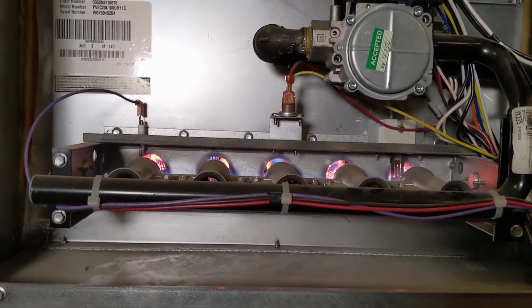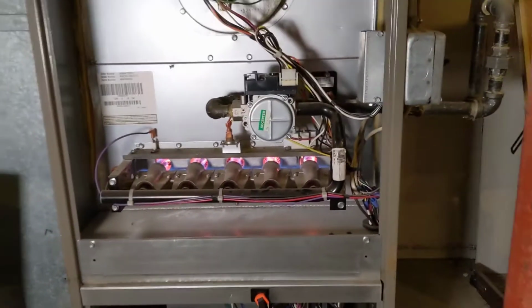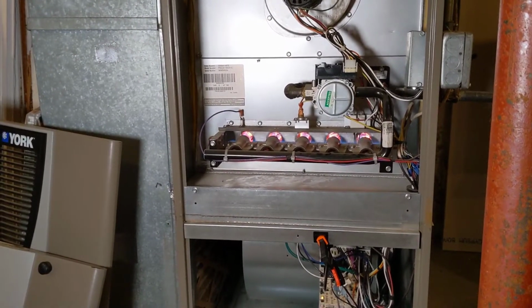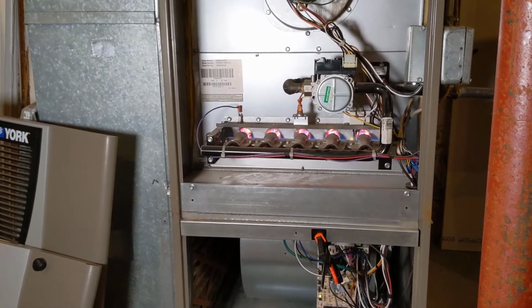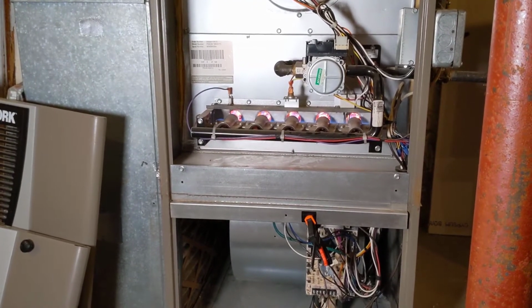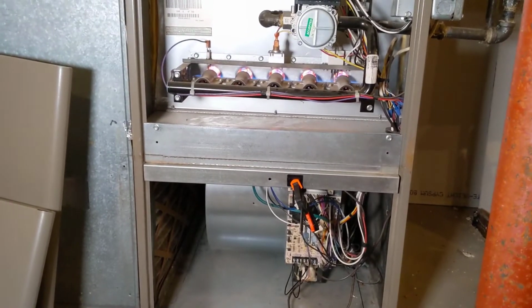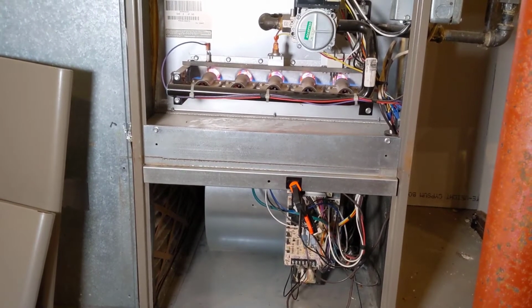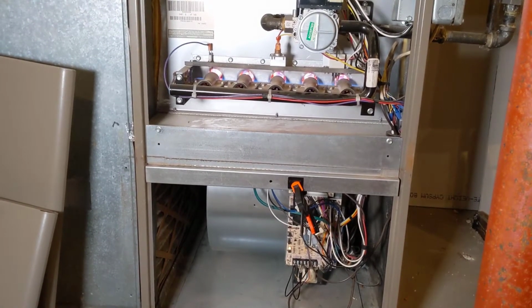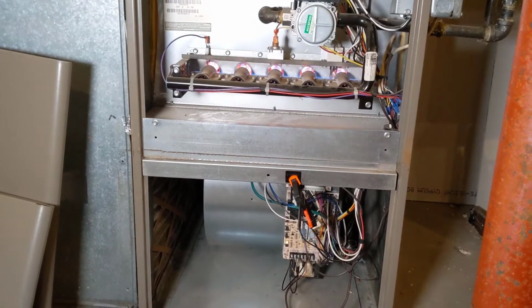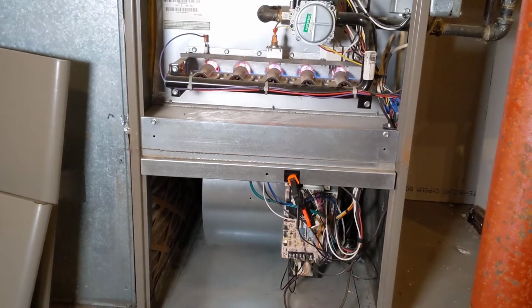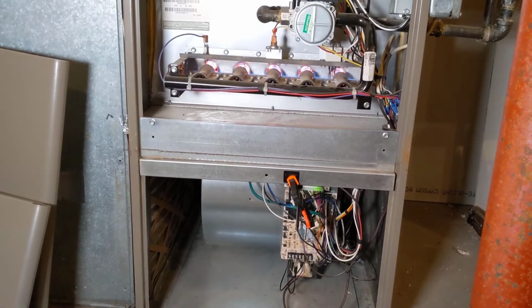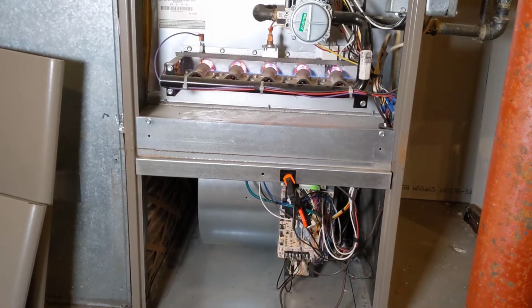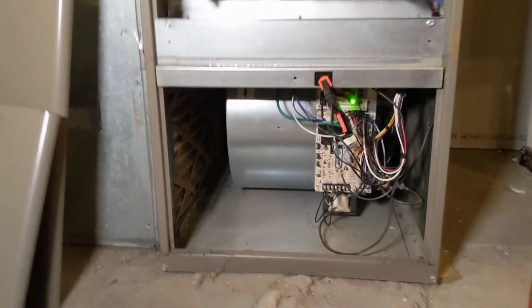So the next step should be that once we get to the right temperature, our big blower motor should start turning on. So let's give that a second. Heard the relays click. And here comes the blower. And there we go. Now we have the blower motor running and we have heat coming up through our plenum.